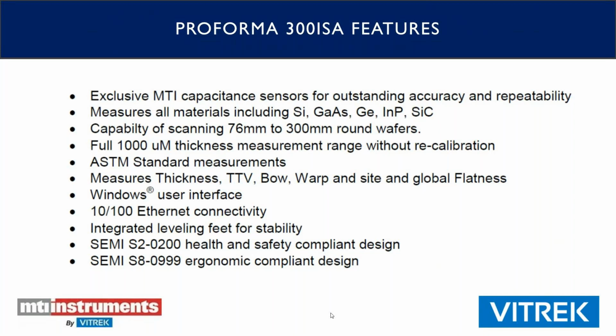It gives you a full 1,000 micron measurement range without recalibration. You can actually measure thicker wafers than this with probe adjustments, but the measurement range, the variation, is up to basically a millimeter in thickness variation there. So it does meet all the ASTM standards.